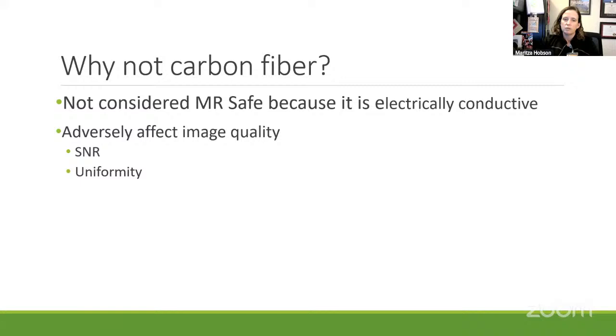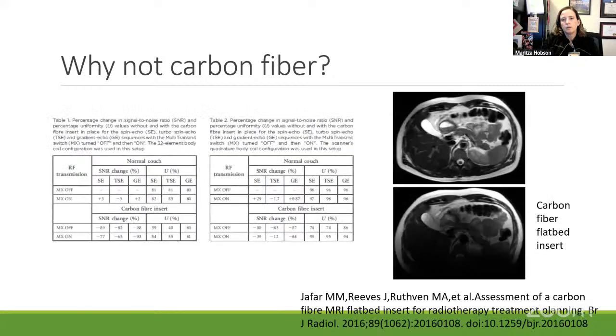Why do we not use a lot of carbon fiber with MR conditional or MR safe RT immobilization devices or accessories? It's because it's electrically conductive and may potentially burn a patient. It can also adversely affect the image quality, so the signal to noise ratio or the uniformity. Jafar et al. first looked at phantom studies where they showed that for 2 different coil configurations, SNR and uniformity both decreased when the carbon fiber insert was present. You can see those numbers in these tables. It's easier to see visually that when the carbon fiber flatbed was inserted, there's a huge shadowing artifact on the bottom image right here, compared to when there's no carbon fiber.